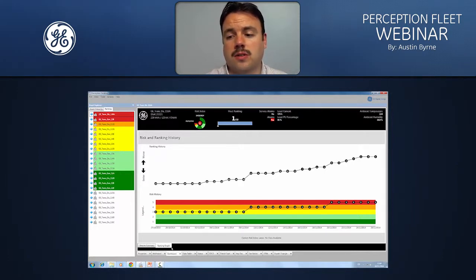If I hover the mouse over the point, it will show you why it's considered to be a risk index of 5. You can see for this latest measurement point that it's saying that there's no data, and that's because there's been no data that's been taken from the online monitor for a day. So we still apply a risk index of 5 because that was the last known condition of the asset, but we let the end user know that this is not a new calculation, this is a historical risk index. If I go to the one prior, you can see on the 24th of November, a risk index of 5 was calculated, and you can see the reason for that calculation.